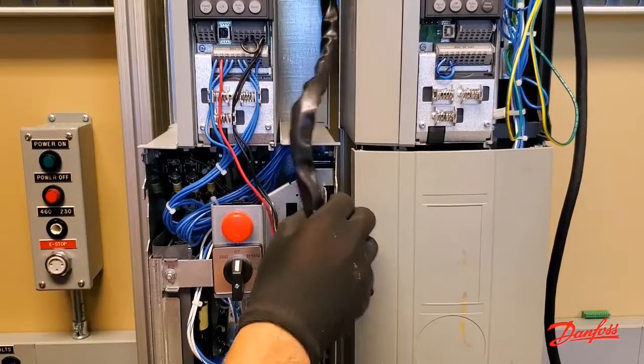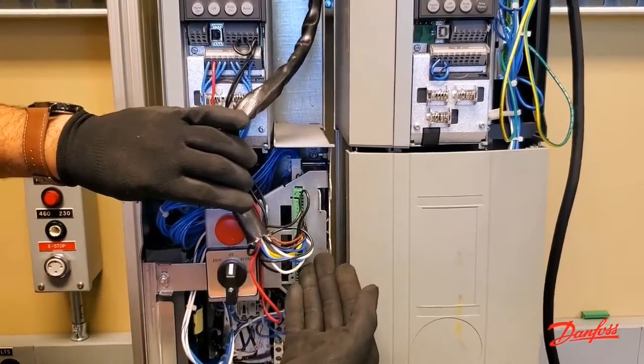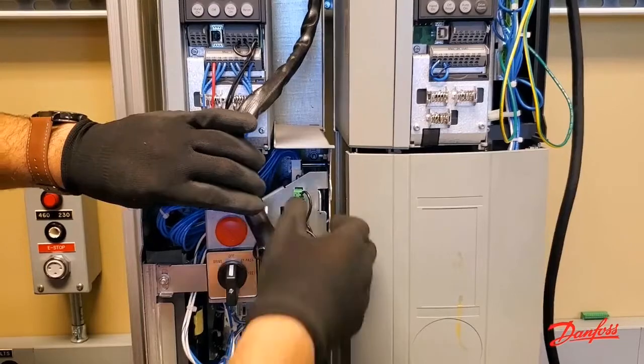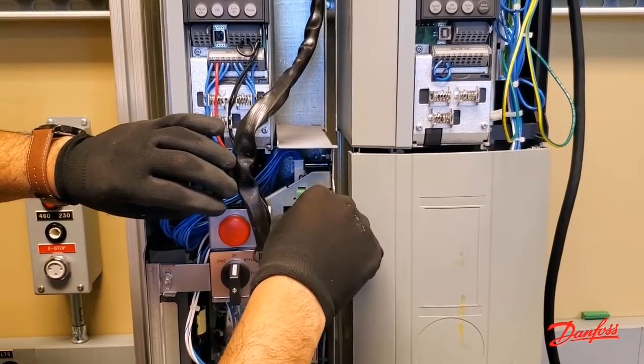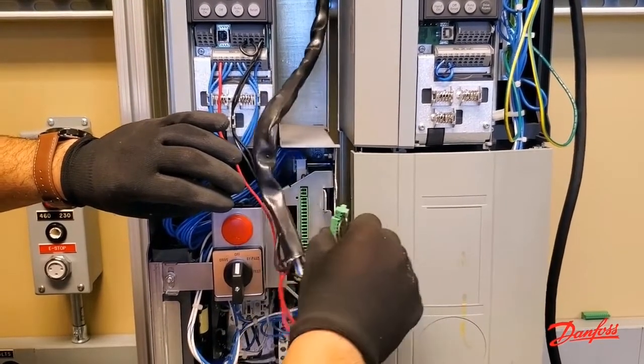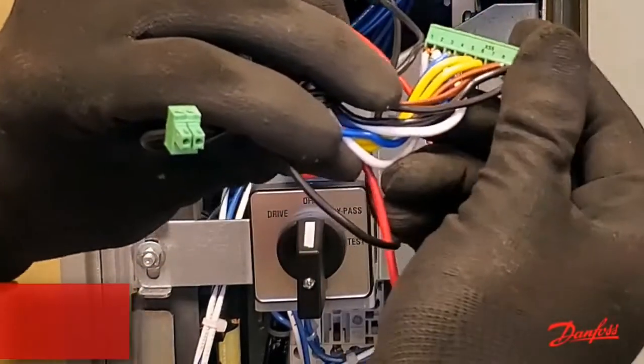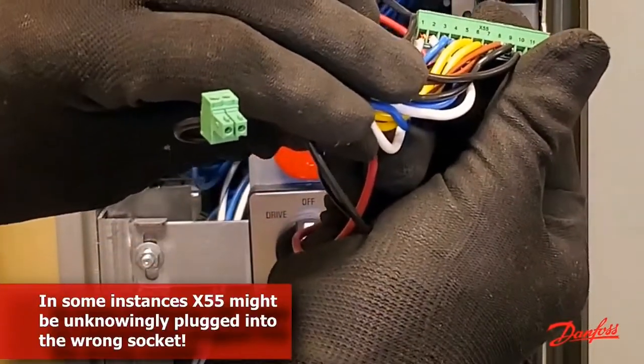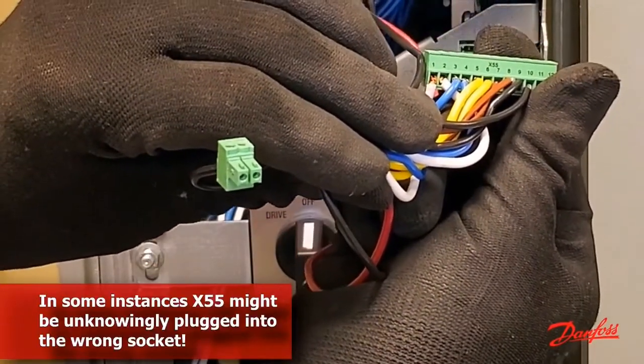The physical location for all three of these connections is a terminal block labeled X55, sometimes MK100, at the bypass board. Notice how the terminal block itself is labeled X55, as should be the socket on the board. Always double check.